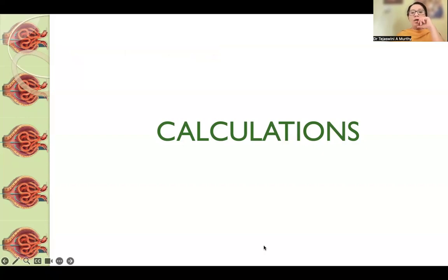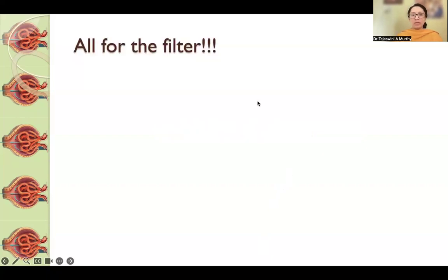So I will only talk about two important calculations which are essential in this. Both these calculations are important to help prolong the life of the filter. A normal CRRT filter can last up to 72 hours or up to around 770 liters of blood filtered.